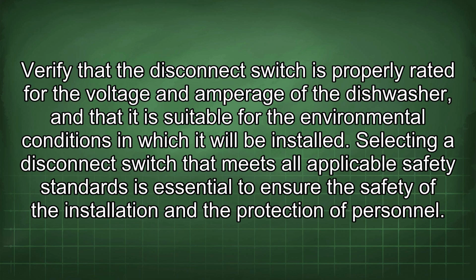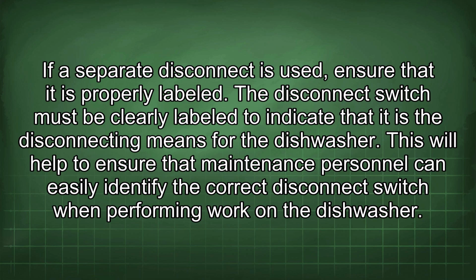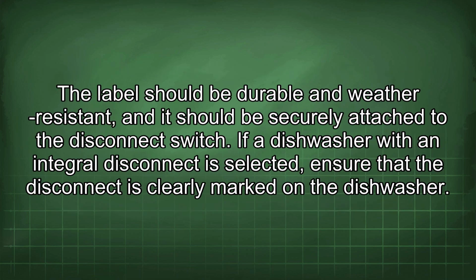If a separate disconnect is used, ensure that it is properly labeled. The disconnect switch must be clearly labeled to indicate that it is the disconnecting means for the dishwasher. This will help to ensure that maintenance personnel can easily identify the correct disconnect switch when performing work on the dishwasher. The label should be durable and weather-resistant, and it should be securely attached to the disconnect switch.